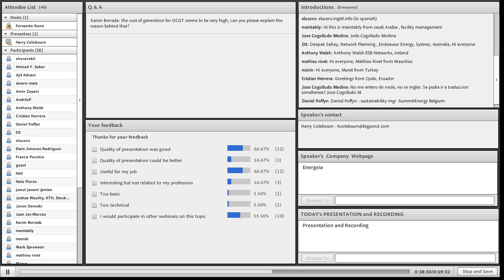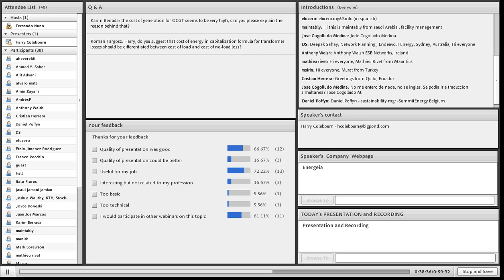The next question from Roman Targos: would you suggest that the cost of energy in the capitalisation formula for transformer losses should be differentiated between the cost of load losses and the cost of no-load losses? Yes, absolutely. It's clear that the two costs are very different and they influence different aspects of transformer design. The no-load losses would apply to the design of the core material, and the series losses apply to the conductor and winding configuration. It is particularly important that those two aspects of transformer design be considered separately, and that appropriate values for the losses for both components be used to determine the overall transformer design.